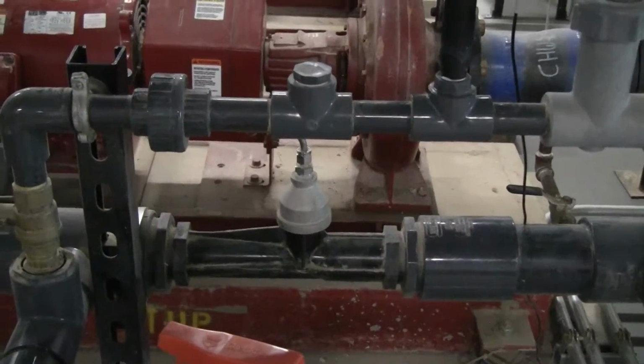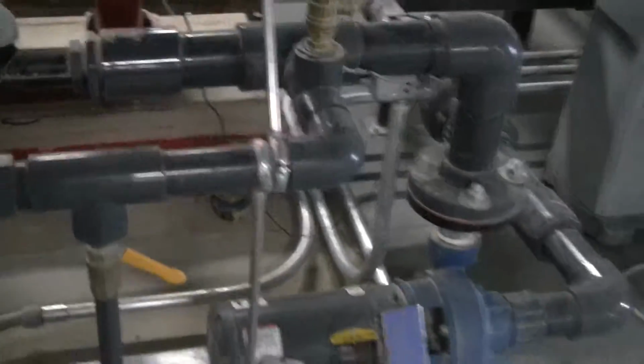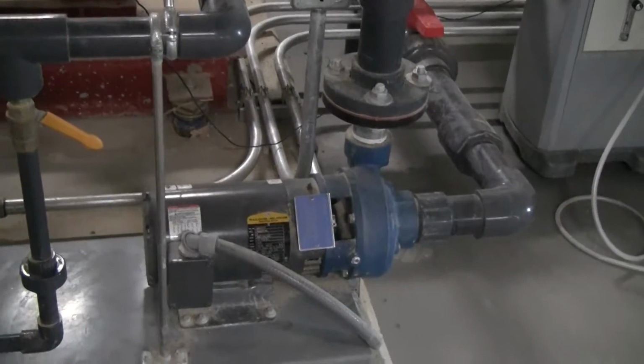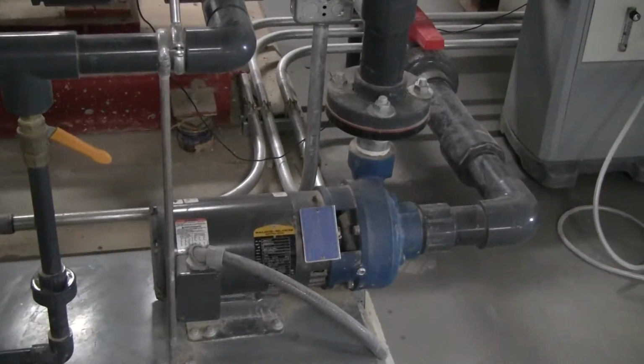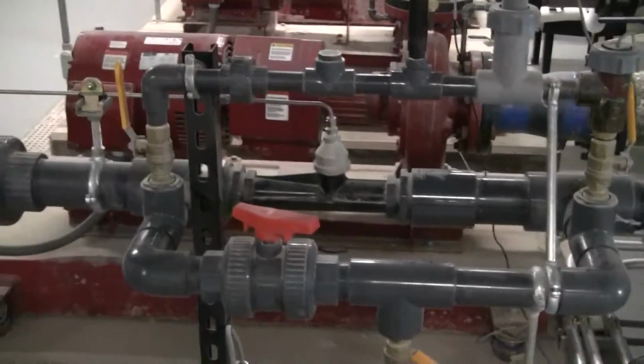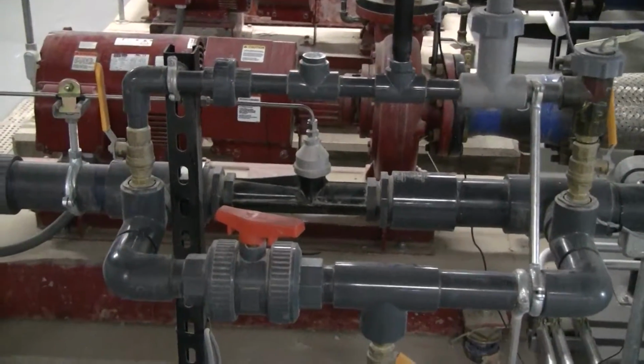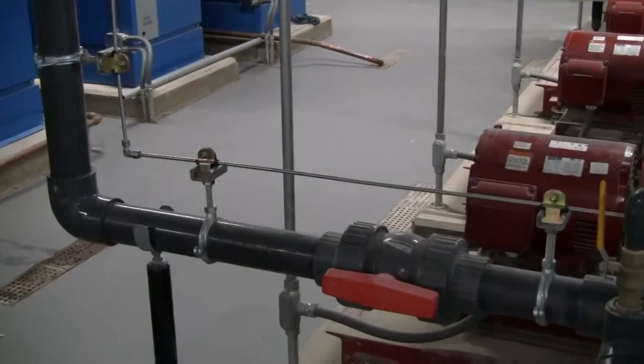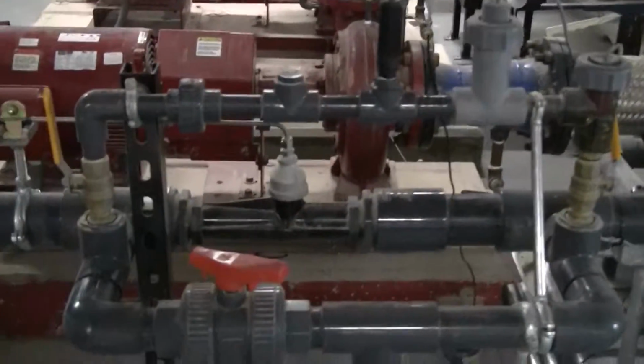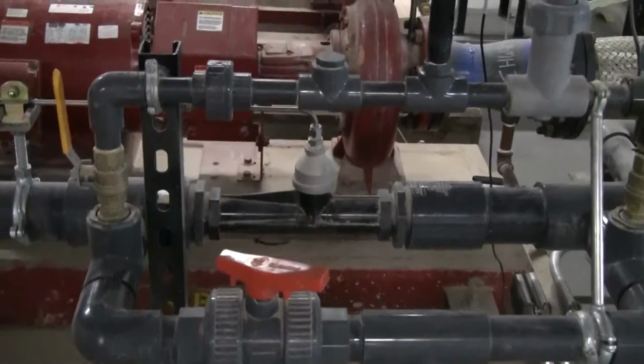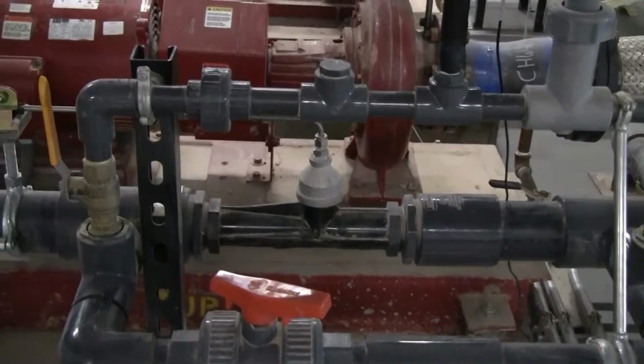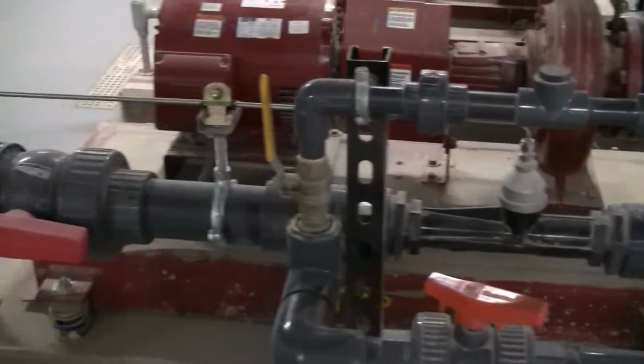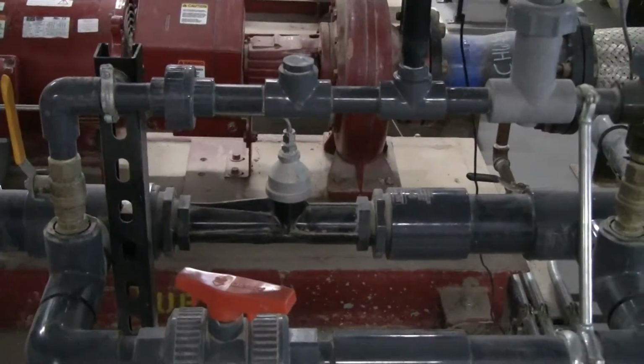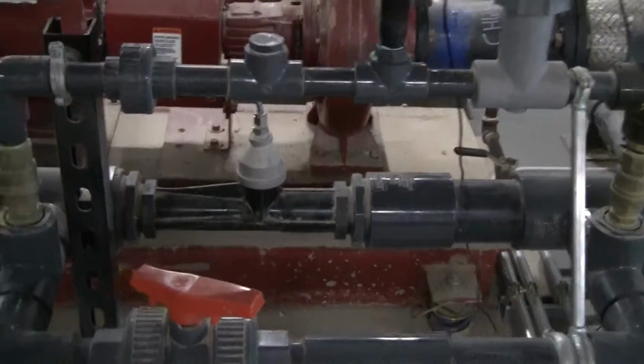The gas comes in here into the venturi. The main pieces that we have now are the circulation pump, where we're pulling water out of one side of the cooling tower sump, sending it through our sample loop, venturing the gas in under vacuum, sending it back out to the other side of the cooling tower. We have the sample loop here where we have the venturi. That is creating a pressure differential with a vacuum to pull the gas into the water. Then we have proper velocity for mixing the gas in the water to try to get approximately 95% mass transfer balance.